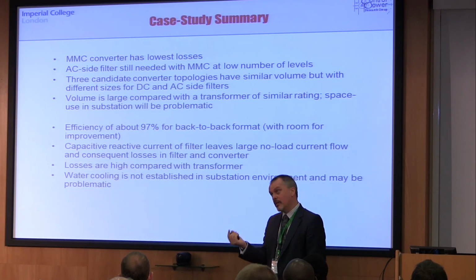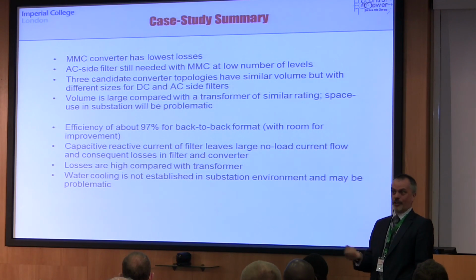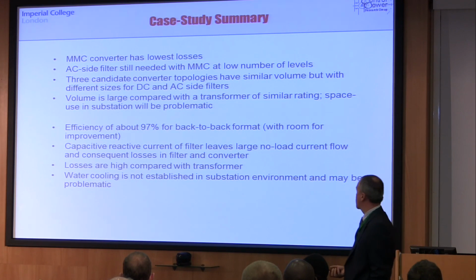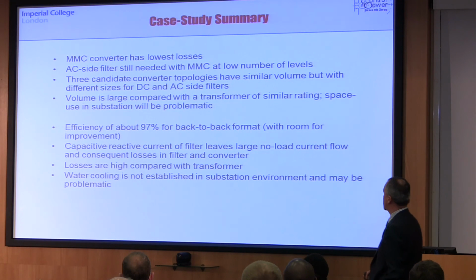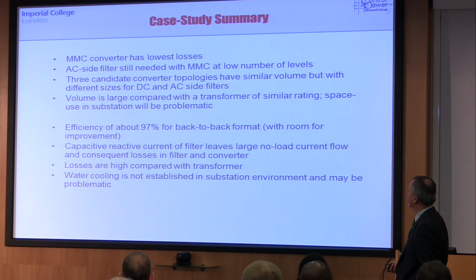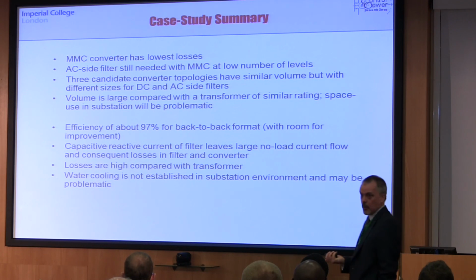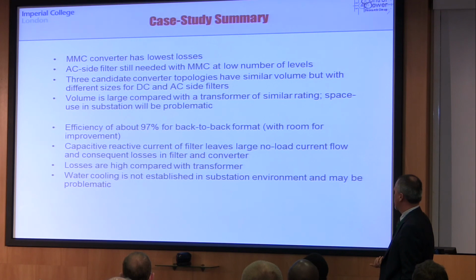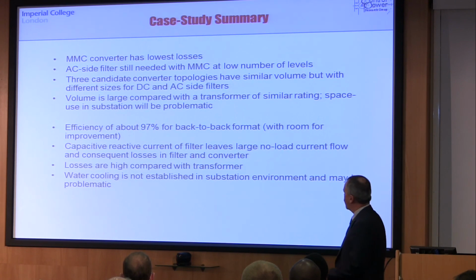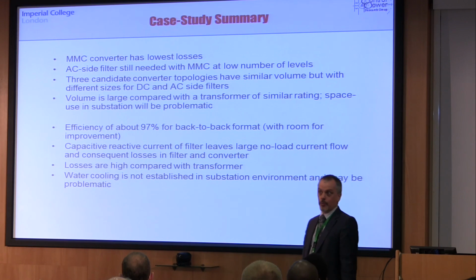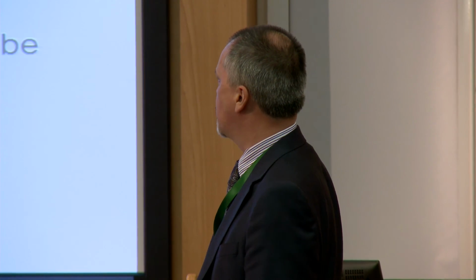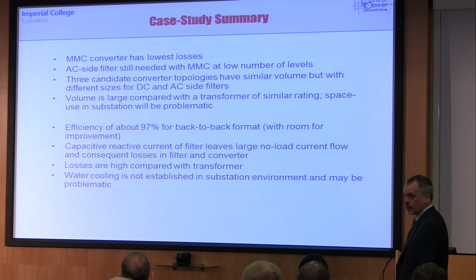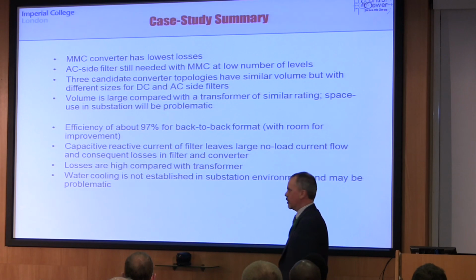So on that, we find the volumes overall quite challenging for use in a substation environment, shipping container-sized power converters. Not a lot of space to fit those in existing power stations, substations. Probably the MMC wins overall, although big DC link or DC side capacitor use. Back-to-back format, we could probably on that study achieve 97 and a bit % efficiency, and we could probably improve on that. But I think there's some way to go before power electronics of these sorts of power levels and tens of kV are going to come in with the efficiency and the size that we require of them. And a final point, that was assuming we could get away with water cooling, and there's no history of using water cooling in substations.